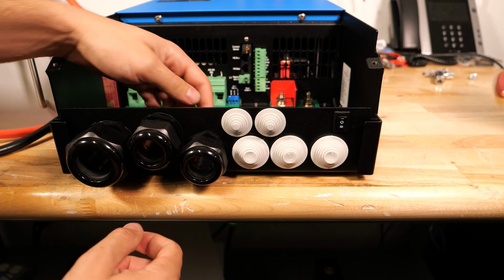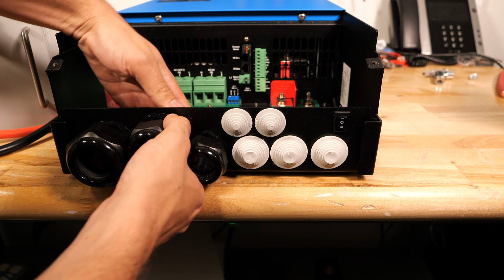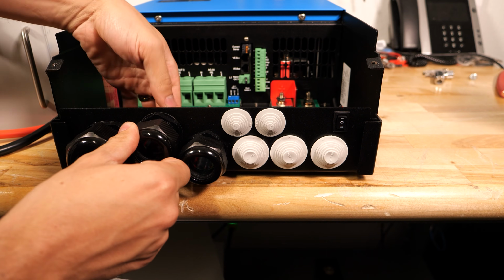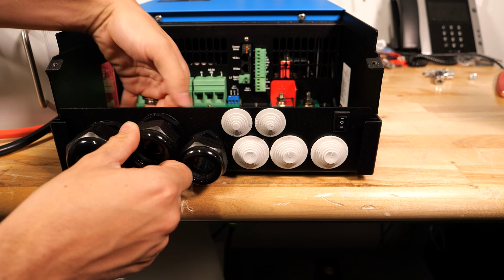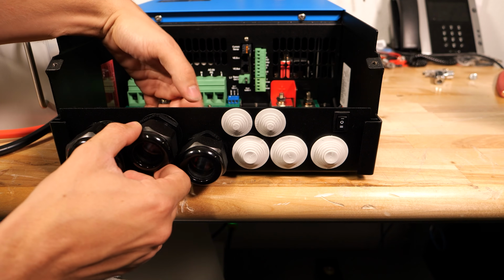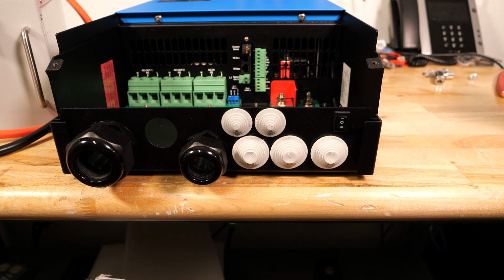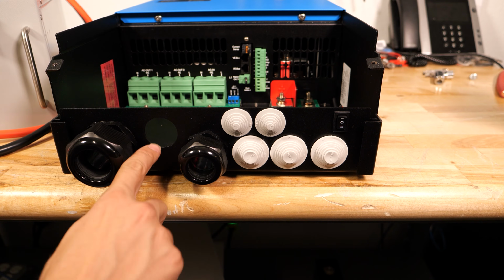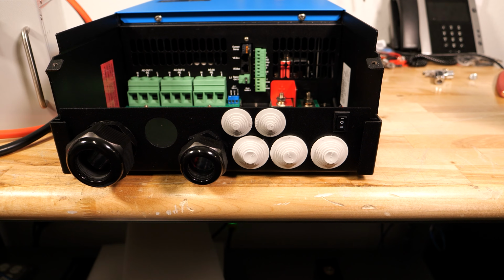I don't totally like these cord grips. They're really designed for SO cord, but if I were wiring this up, I'd probably use seal-tight conduit instead. I know in Europe, where Victron is originating from, they use cords pretty frequently, but for me, again, I like conduit, and I could easily land a 1-inch conduit on here if I wanted. Now, the one here on the left is probably 1.25 inches. I don't know that I'd really use that.